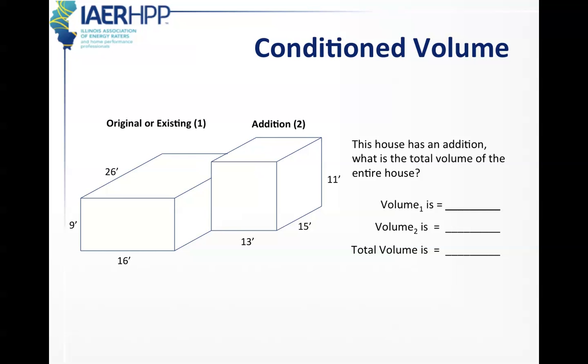Now, you might come up against a house that looks like this with two distinctly different shapes. Just like we added together the areas of rectangles, we can add together the volumes of different shaped cubes. The volume of number one is 16 feet wide by 26 feet long by 9 feet high, which is 3,744. The volume of number two, 13 times 15 times 11, gives you 2,145. To figure out the total volume, we add the two together, and we would get 5,889 cubic feet.